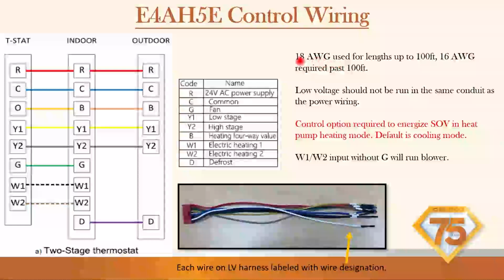Of course, 18 gauge thermostat wire, up to 100 foot. Low voltage should not be running in the same conduit as the power wiring. Please keep low voltage away from line voltage because it will interfere with the EMI. W1, W2 input without G will run the blower. So that's different too. We don't need a G call to run the blower with our heat strip commands. The board will turn on. And our purple wire, defrost: when the outdoor unit goes into defrost, it will energize D, which energizes the heat strip in defrost mode.